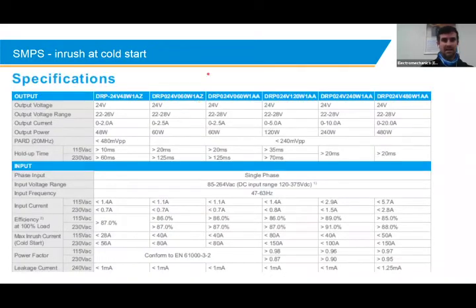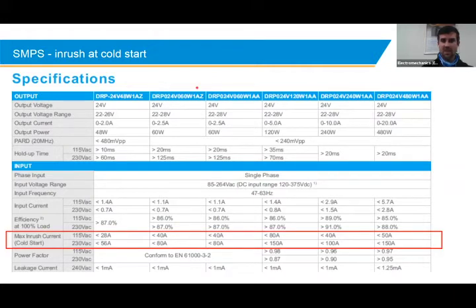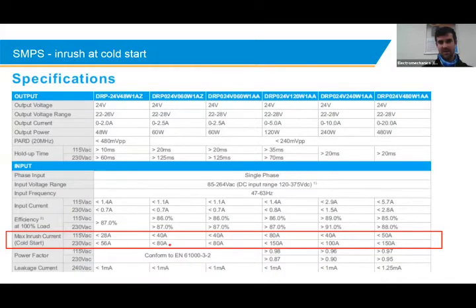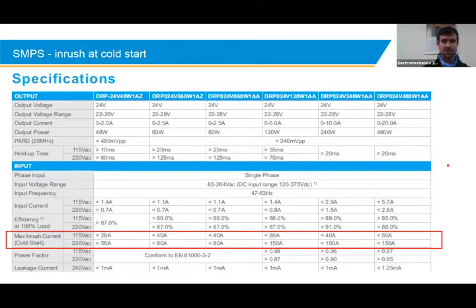Just highlighting the specs of the inrush current, I'm just going to look at our DRP series. So you note that they don't specify a particular value, but rather that it won't exceed a certain amperage. So a typical C-curve breaker, you know, is 5 to 10 times the rated current inrush. At a 6 amp breaker, you're looking at 60 amp inrush that you can have on a 6 amp breaker, basically. So just something to take note of and maybe to be aware of when you do specify a circuit breaker or a power supply.